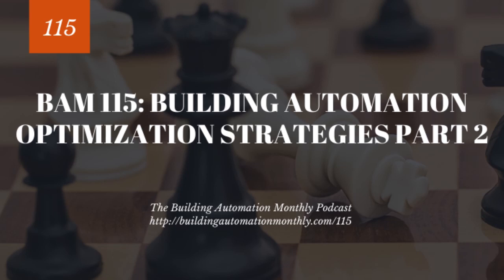That means for humidity sensors, CO2 sensors, CO sensors, airflow sensors, and pressure sensors, you want to go through the range as much as possible. What you don't want is to calibrate a sensor to the current measured value only to realize there's an issue as you get towards the higher or lower end of the range. You want to be able to move through the entire sensor range accurately.